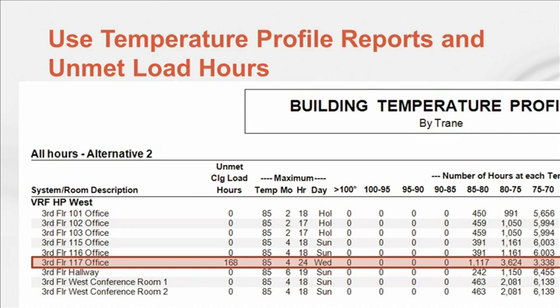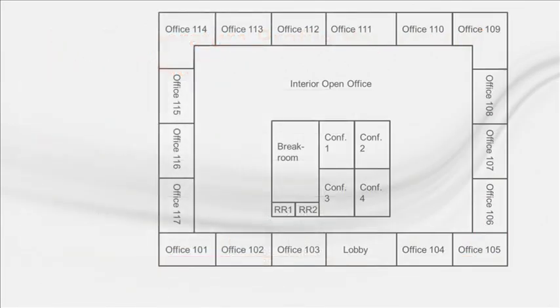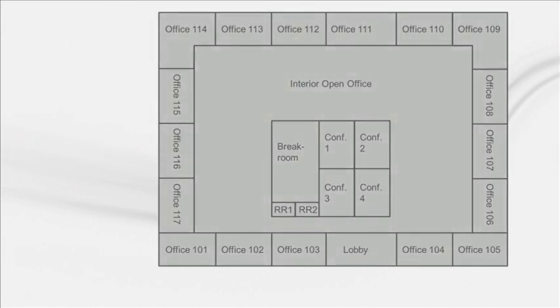Let's get back to our example building. We can use simulation software like the Trane TRACE 700 program to size indoor units and identify which zones to group together on the same system. In this case, we could group all of the zones together on a single VRF system. This is actually one of the more common mistakes we see. Remember that the total load, excluding ventilation, is 51 tons and greater than a single VRF outdoor unit can provide.